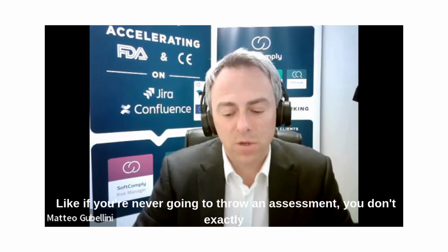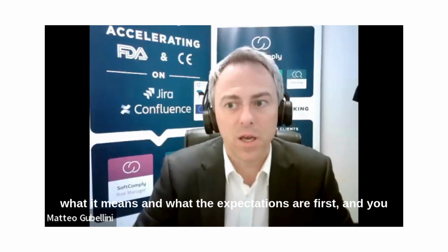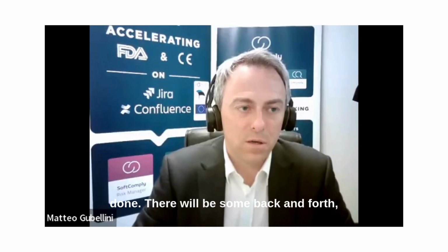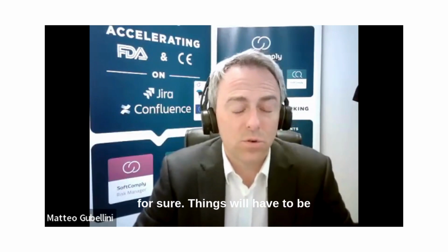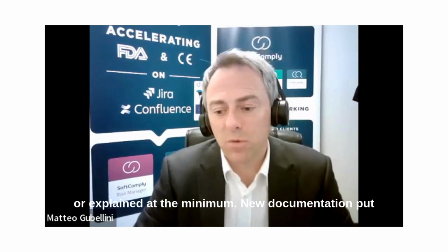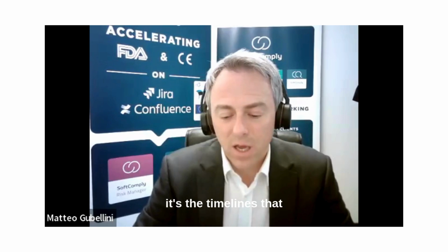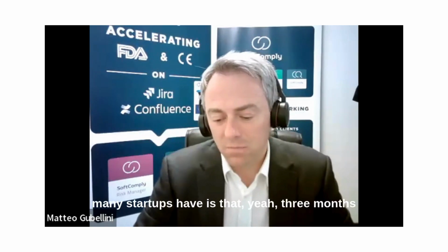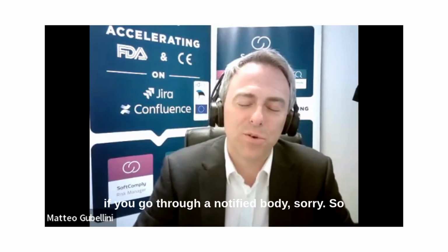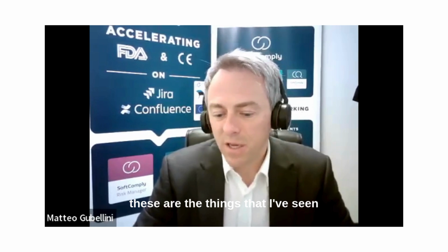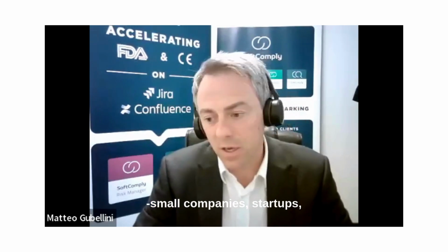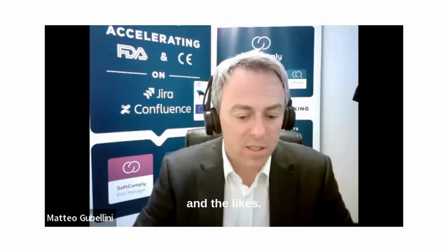If you've never gone through an assessment, you don't know exactly what it means and what the expectations are, and you don't realize that it's not a process where you submit and it's done. There will be some back and forth for sure. Things will have to be modified, changed, or explained at the minimum, with new documentation put together and clarifications. The timeline that many startups have is that in 3 months it's on the market. Not if you go through a notified body, sorry. So these are the things that I've seen the most, and this is for medium, small companies, startups, and the like.